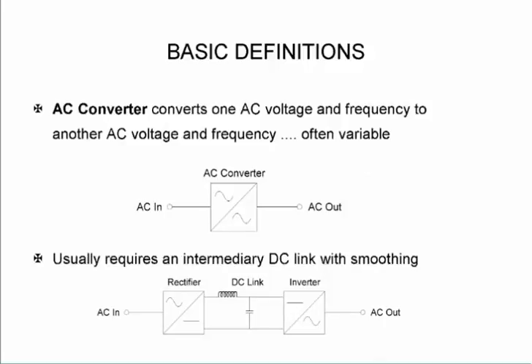In an AC converter where it converts one AC voltage and frequency to another AC voltage and frequency, there is normally an intermediary DC link with some smoothing. If you take the example of a variable speed drive it can have a single phase input that will then be rectified, then have a DC link, and that DC with the inverter will then be converted to a single or a three phase output supply.